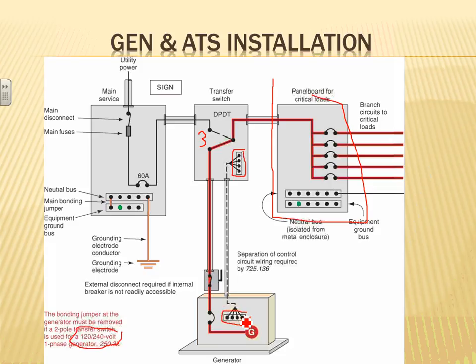Well, what they would do is either you have a resistor bank where you can throw the load onto these generators and test them. We don't interrupt the power. That's what they do, I believe, in hospitals. You don't want to mess around with the hospital. So they have another source, another load where they can test their generators. They can even put reactors to simulate the inductive reactance too, reactors and resistors. So they load them other than the hospital. Load banks, yep, load banks.